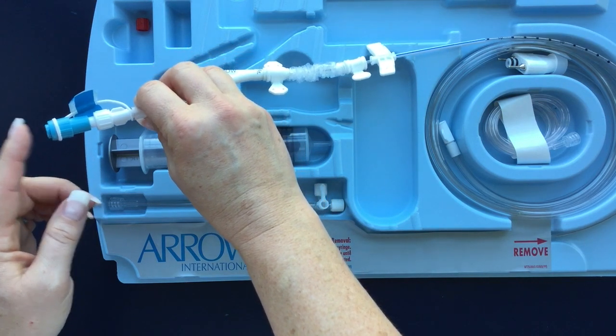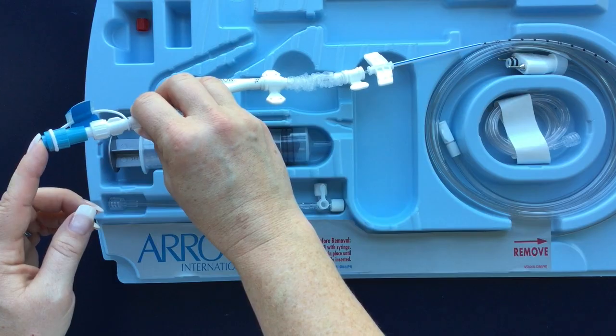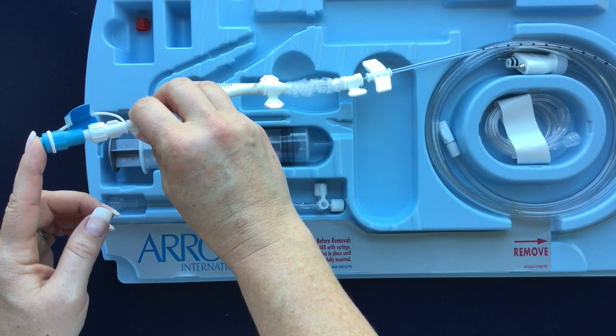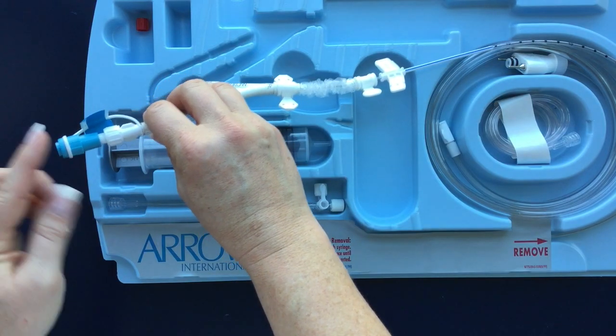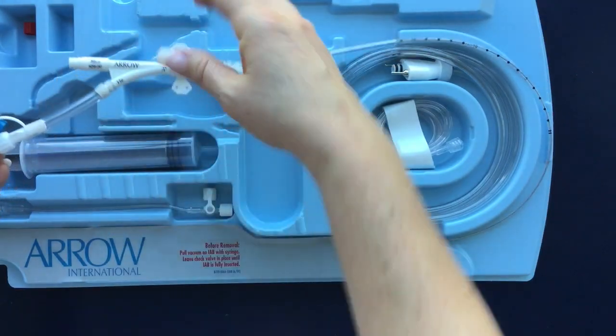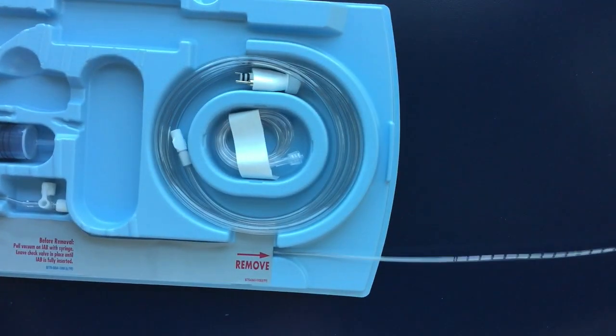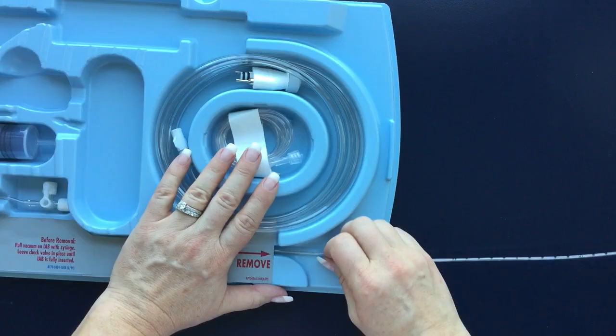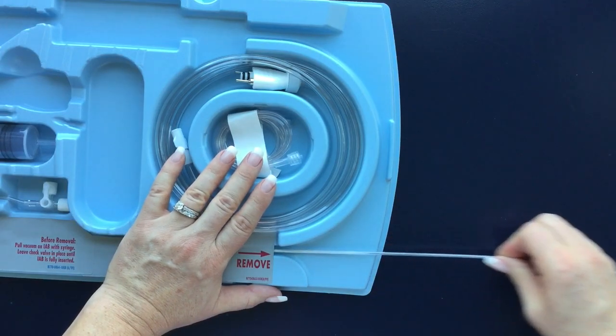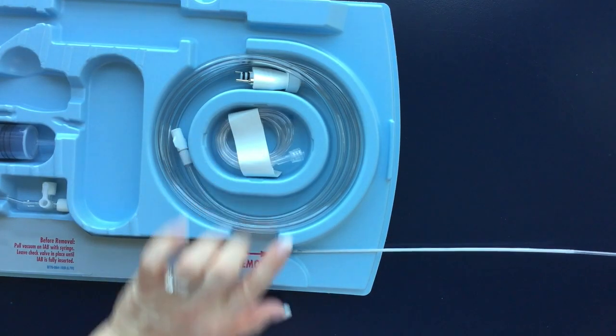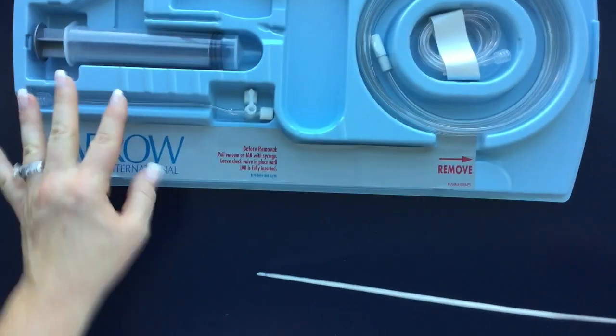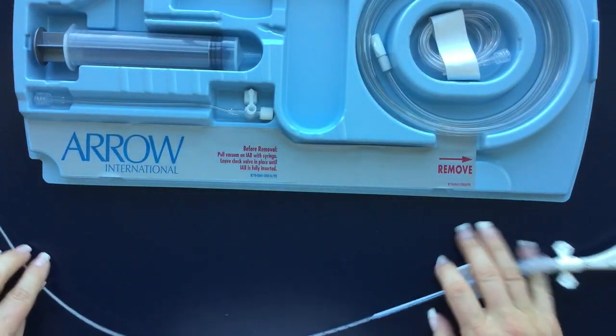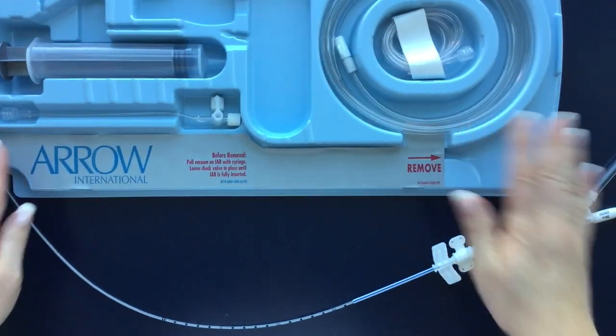If at any point before the catheter is inserted fully into the patient, that one-way valve has come off, reconnect and do that negative prep again. Now I'm ready to pull my balloon from the tray. I'm going to stretch it out parallel and straight and pull gently on the catheter until I see the tip pass the label. Now I can bring the catheter back up in front to continue prepping.